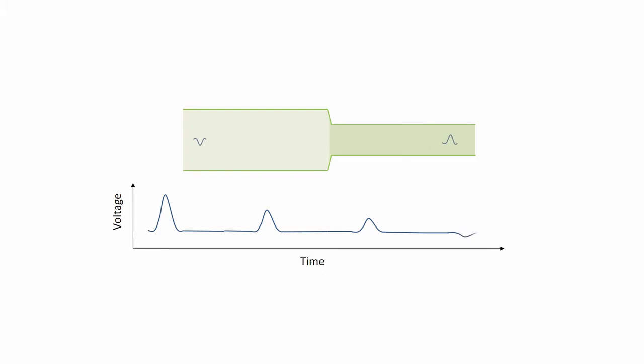So on a normal line, if you like, it has a fingerprint. This pulse will continue every couple of seconds down the line and come back, and that reflection basically overlaps itself if it's healthy. So every reflection will come back on that line and should remain the same. Where there is a change, which is a discontinuity within the line, it will be seen as a change from its normal, shall we say, and from that point we can measure where that is on the line.